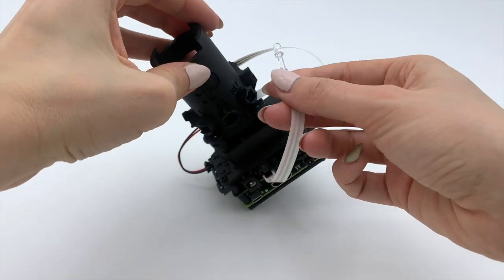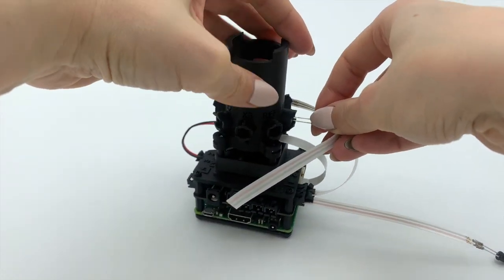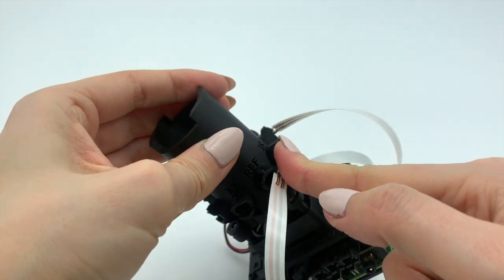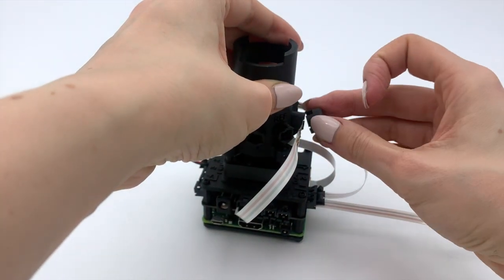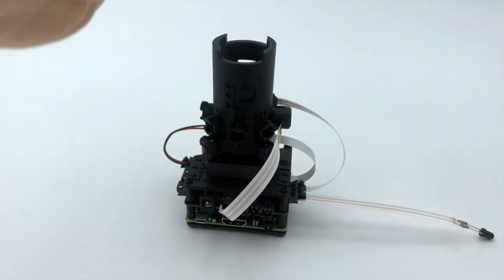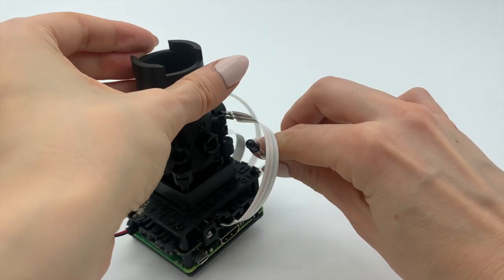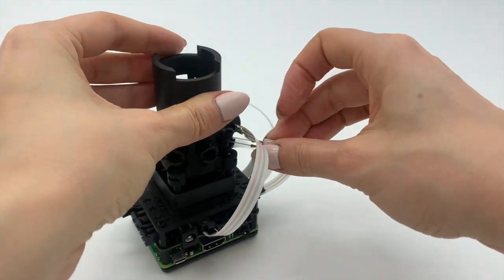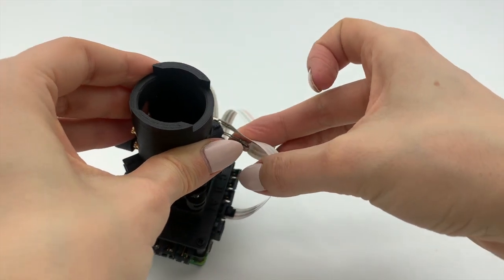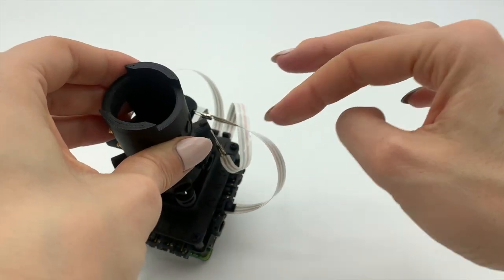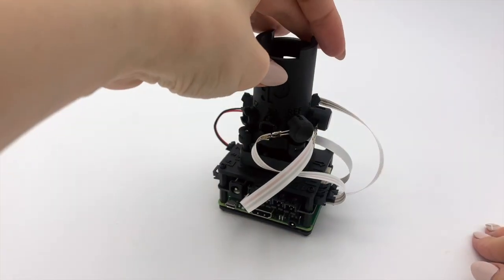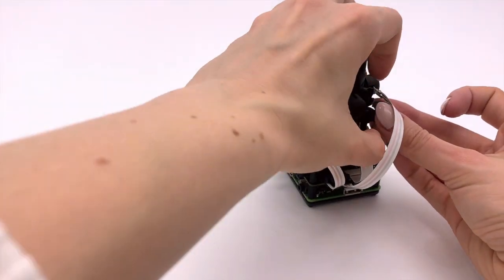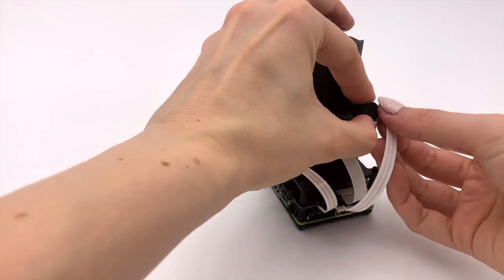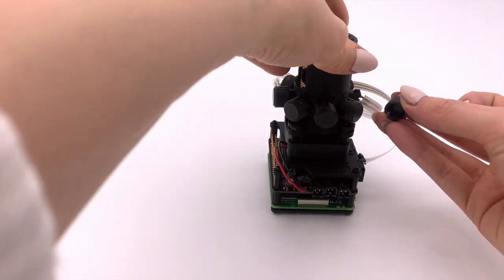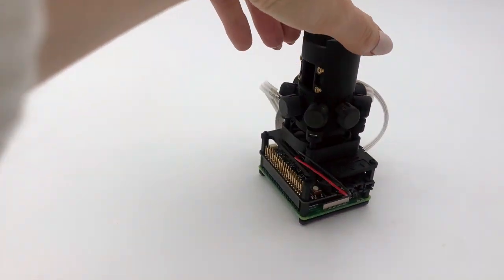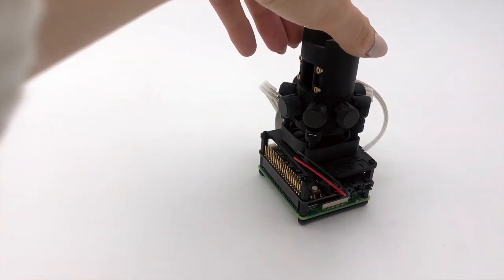Let's take the clear bulb of the IR cable and place it into the pocket labeled IR. Secure a cap on that as well. Finally, take the other dark bulb of the PD cable in channel 1 and fit it into the pocket labeled REF. Orient it 90 degrees so it doesn't interfere with the bulb next to it. Fit the pocket cap on there as well. And put the rest of your pocket caps on as well. You should have something that looks like this.